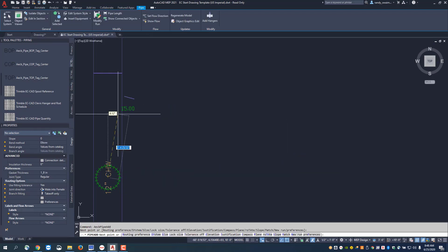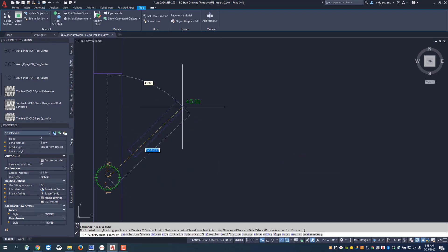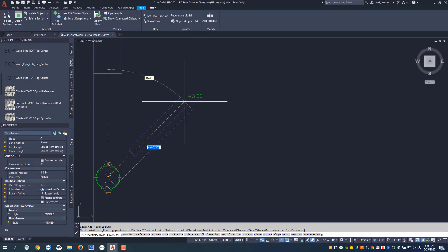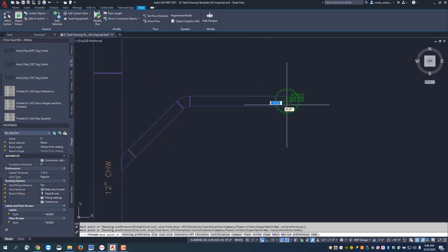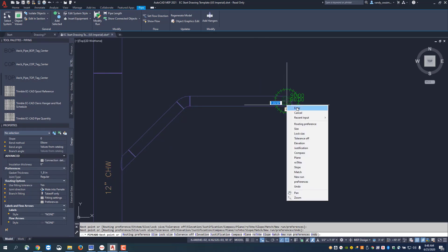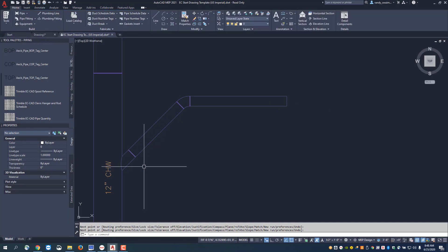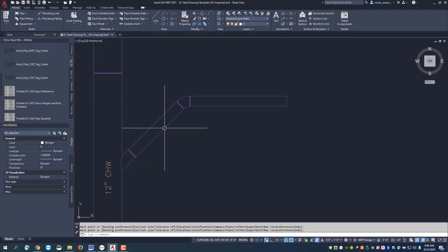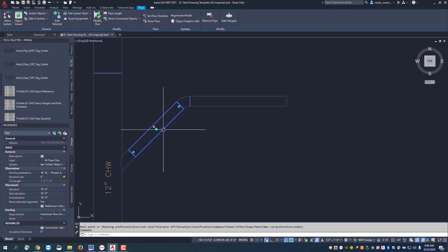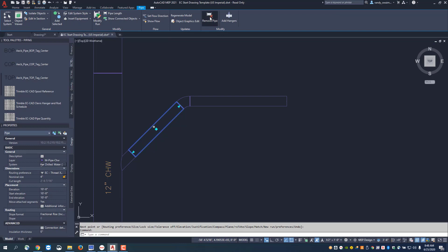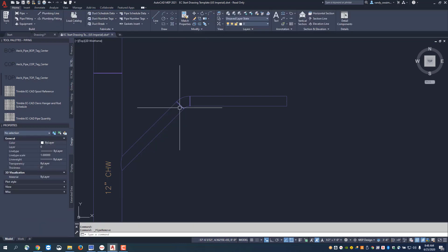Now I want to have this come off at an angle, so I want this at a 45 degree angle. Now I'm going to straighten that back up. You can see that's put in what we call a shaped nipple or a fish mouth. If I want to eliminate this piece of pipe and make this one long nipple, just click onto that piece, go to my ribbon and hit remove pipe. That creates that as one long shaped nipple.